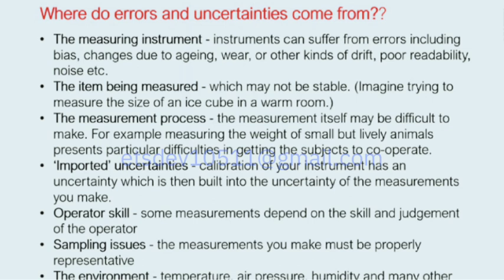Because, for example, if your CRM is to be stored at 20 plus or minus 5 degrees, your room temperature should not have exceeded 25. If on your everyday chart you have 27 or 30 degrees, it will be a non-compliance, because you're supposed to store it at 20 plus or minus 5, whereas your room temperature has gone to 27. So there will be some uncertainty if you use that CRM or that particular primary standard for your analysis. So maintaining the conditions is extremely important.